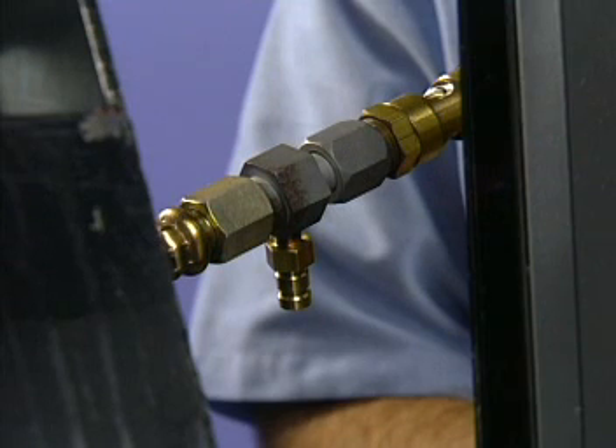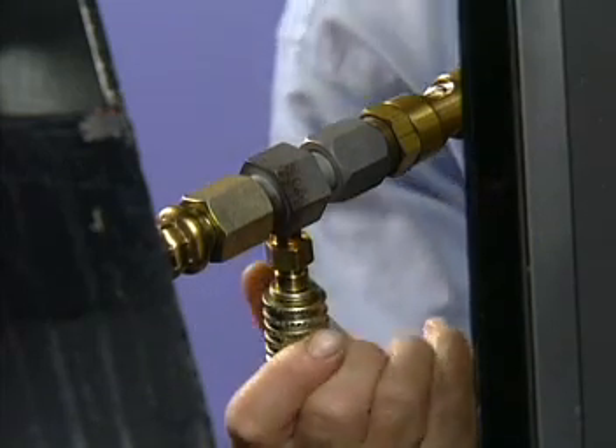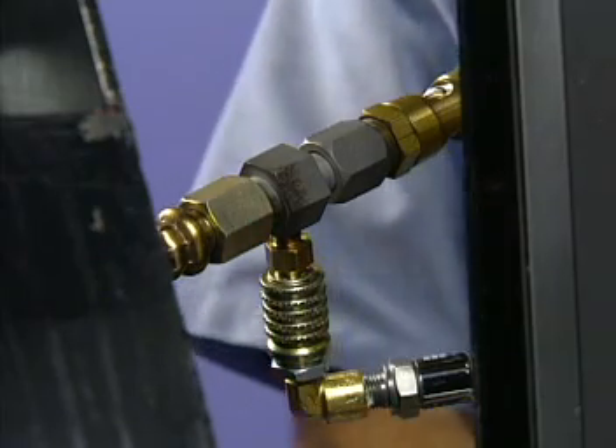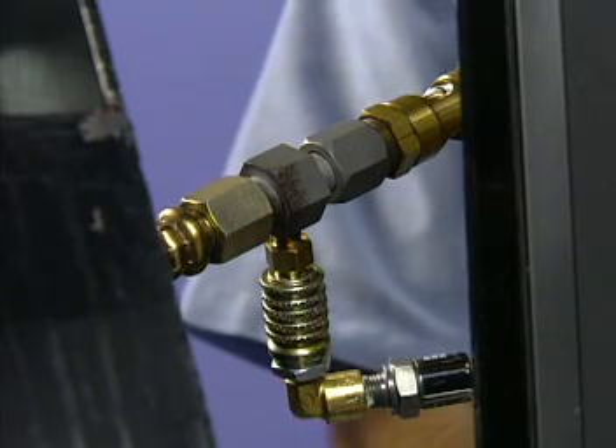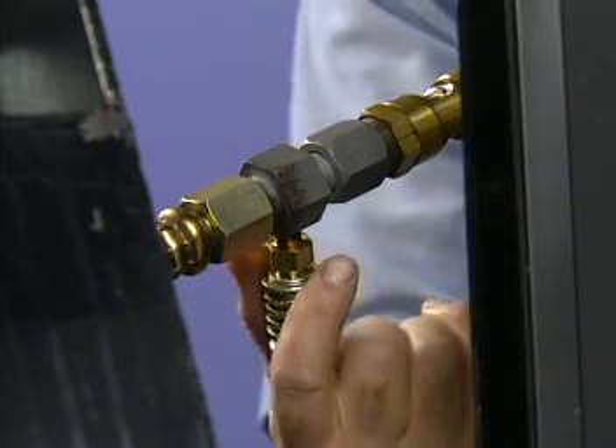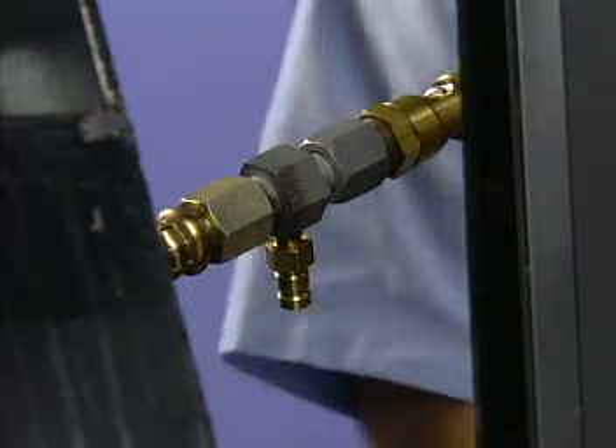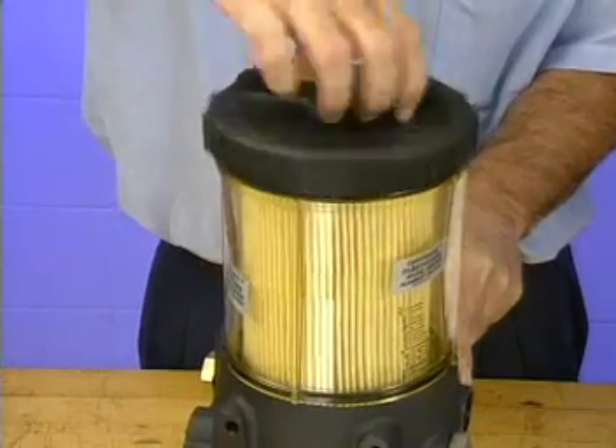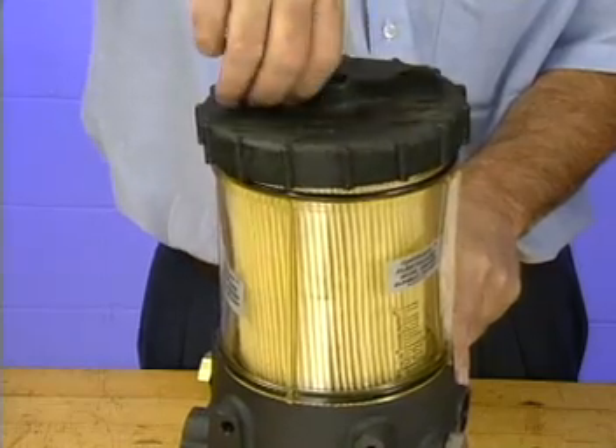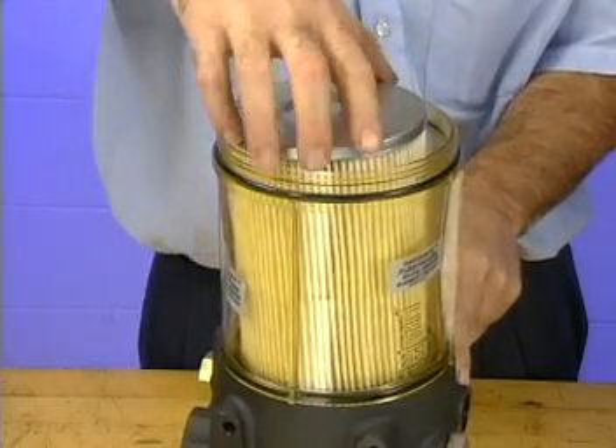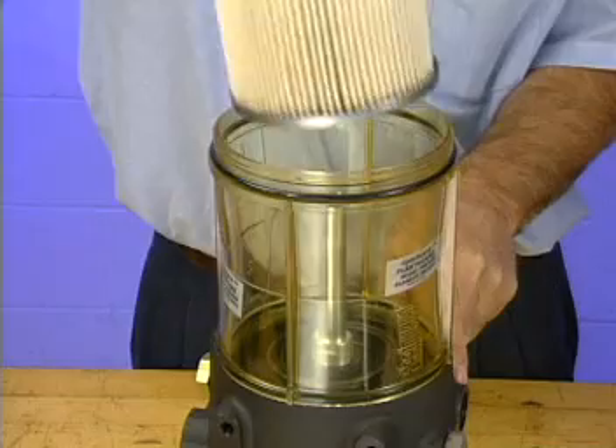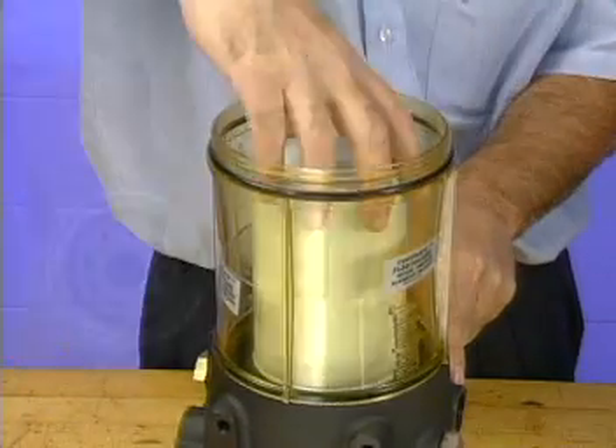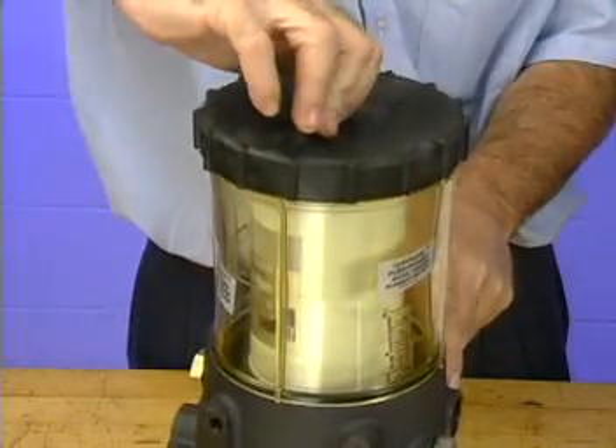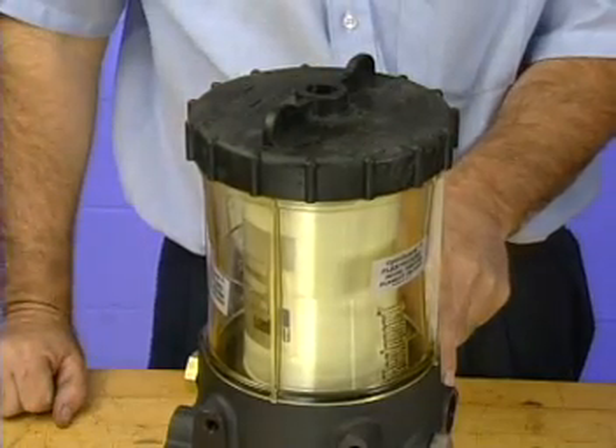If the inlet restriction exceeds the specification, locate the restriction in the fuel supply by moving the gauge from one fitting to the next toward the fuel tank and taking readings. Locate the component or components causing the restriction and repair or replace them as necessary. If the pre-filter is the source of the restriction and a replacement filter element is not available, the pre-filter housing has been designed so a spin-on cartridge can be used in place of the normal filter element.